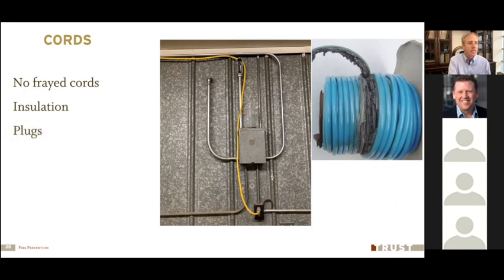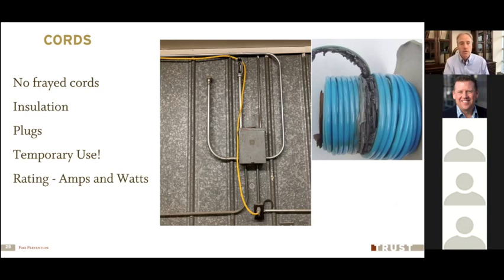I also want you to think about that with your temporary cords. What is your extension cord rated at? It will generally show you the amps that the cord is rated for, and generally we're talking about a 120 volt, single phase cord. So look at what the amps are rated for on that cord and multiply it by the number of volts. If that cord is only rated for 10 amps, for example, the maximum you're going to want to draw through that cord is 1200 watts.